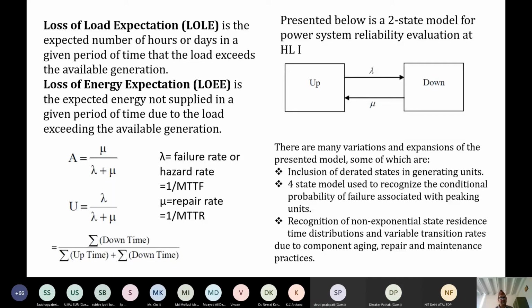And you can see here a two-state model for power system reliability evaluation as HL1, up state and down state. This lambda is called the transition rate from up state to down state, and this lambda is also called failure rate or hazard rate. Means with this rate, the unit will move from up state, operating state, to failed state, and mu is called repair rate. From this rate, the unit can move from down state to up state, means the unit gets repaired with this rate. And A is the availability of the unit, given by mu divided by lambda plus mu, and U is the unavailability, lambda divided by lambda plus mu.